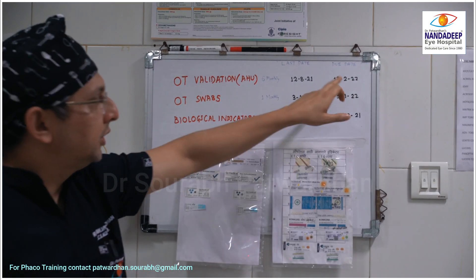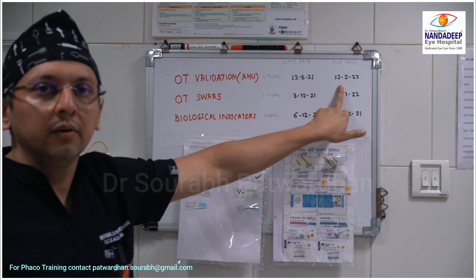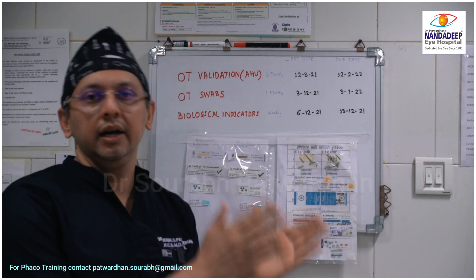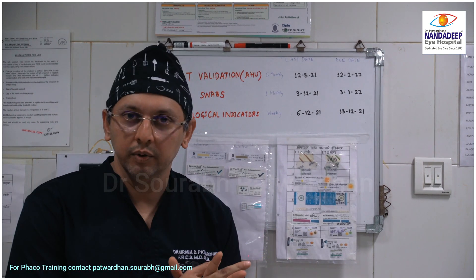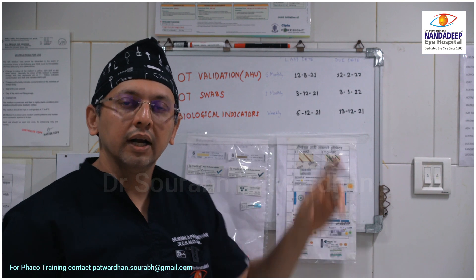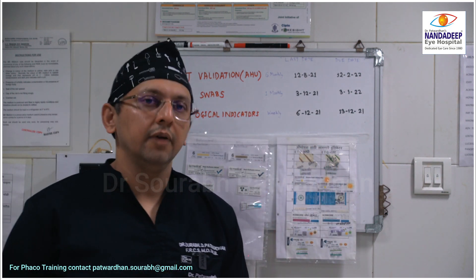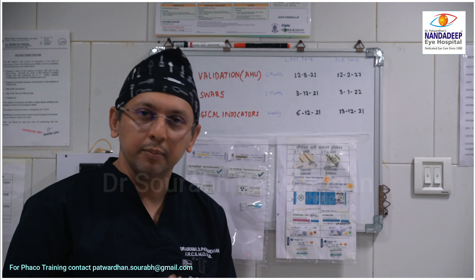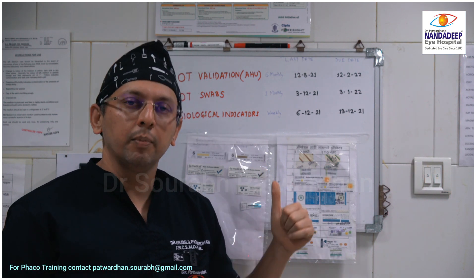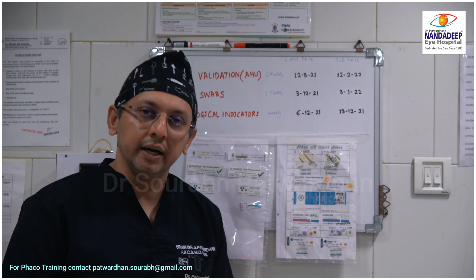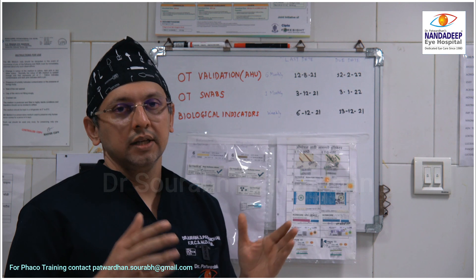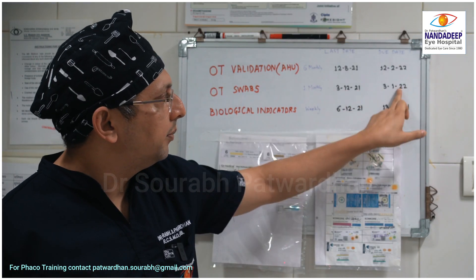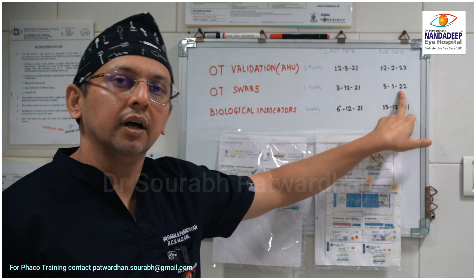The moment I walk in, I should know whether the OT has been validated. This validation is mainly for the air handling units which use HEPA filters. This is very important because even if you have the best air handling unit with a HEPA filter, if it is not properly validated and not properly maintained, it is equally risky. The last validation was taken on this date and the due date is within a month.